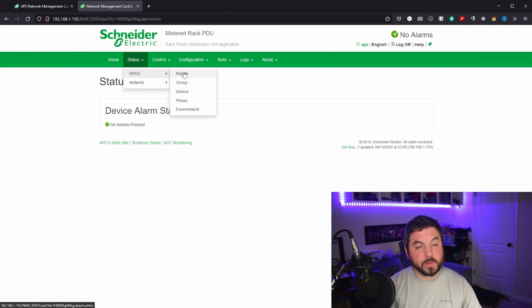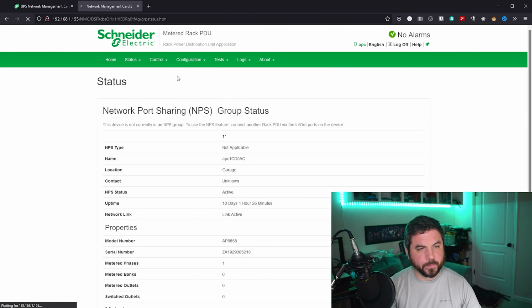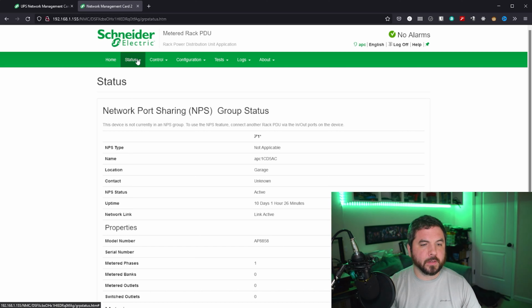The PDU has alarms. This is where you view active alarms that may be going on in the system. If you had more than one PDU, this is where you would use network port sharing. I only have one PDU. I might, in the future, end up getting 2 of these so that I can deliver power to both sides. This is a 20 amp PDU, which falls far underneath the 30 amps that the UPS provides. My UPS has 2 of the 30 amp and 2 of the 20 amp sockets. That doesn't mean go and overload, right? You're not going to get more power out than you put in to it. So just be careful, the PDU should be able to warn you before you get close to overloading your socket.